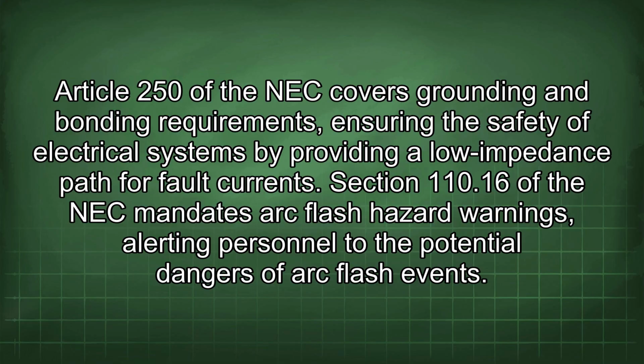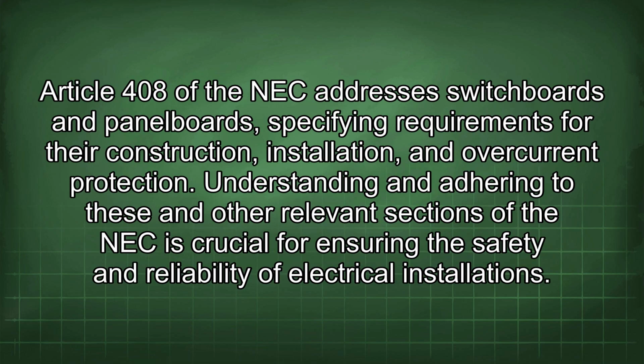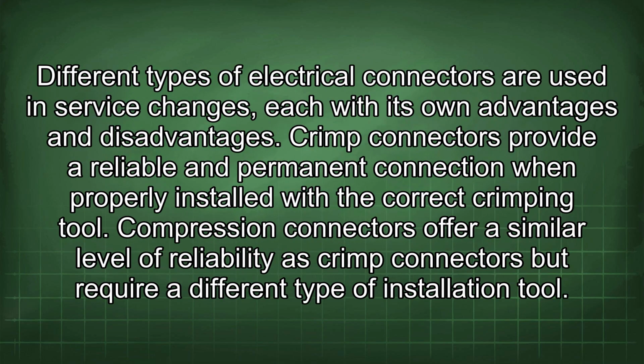Section 110.16 of the NEC mandates arc flash hazard warnings, alerting personnel to the potential dangers of arc flash events. Article 408 of the NEC addresses switchboards and panel boards, specifying requirements for the construction, installation, and overcurrent protection. Understanding and adhering to these and other relevant sections of the NEC is crucial for ensuring the safety and reliability of electrical installations. Different types of electrical connectors are used in service changes, each with its own advantages and disadvantages.